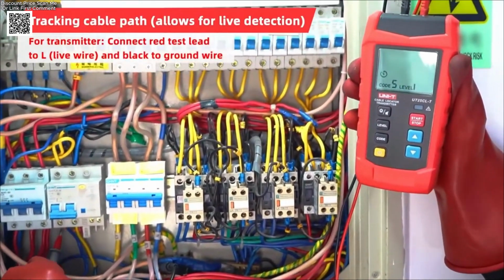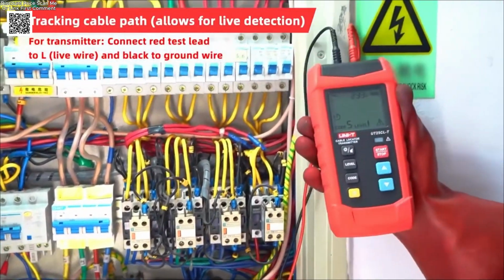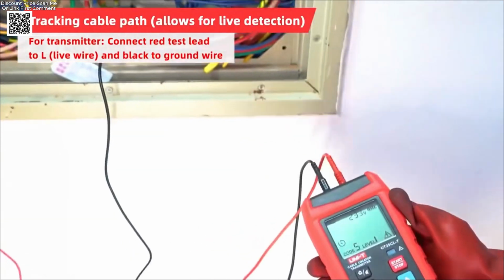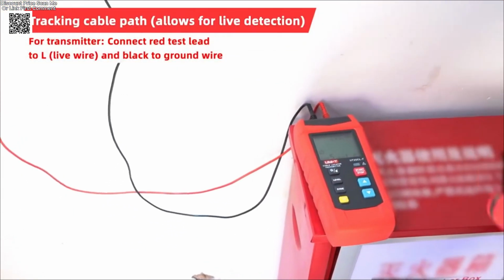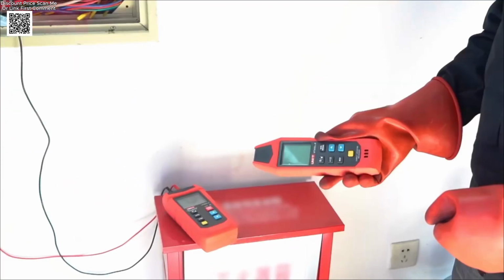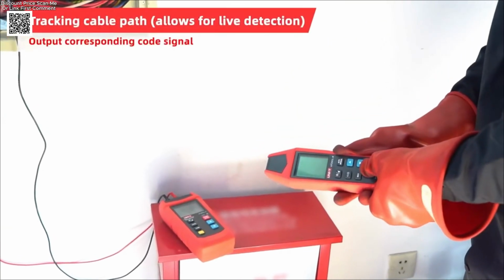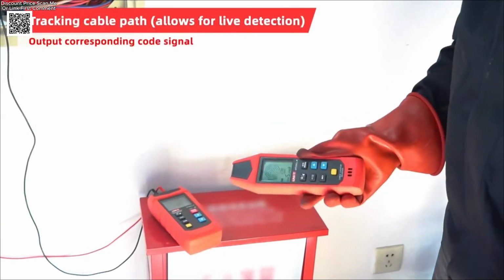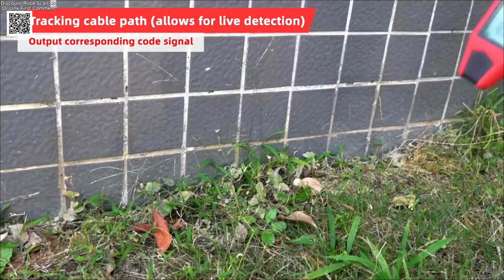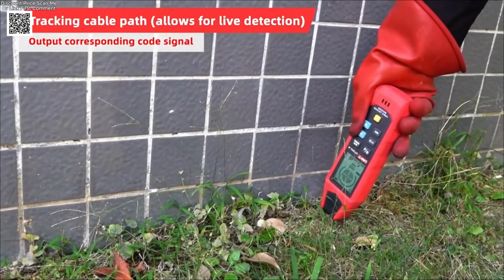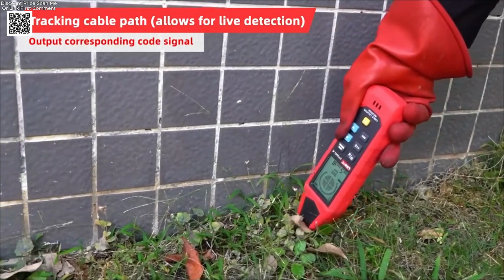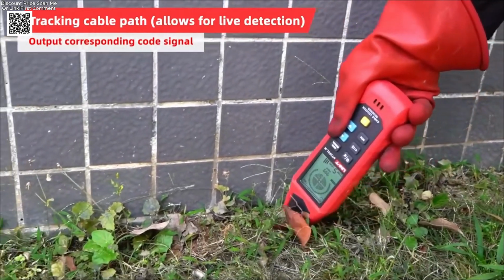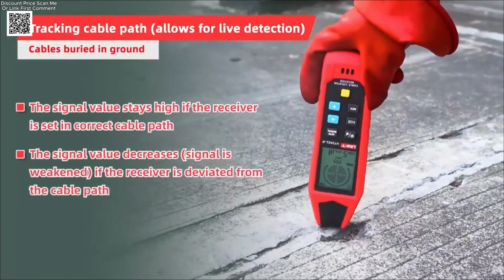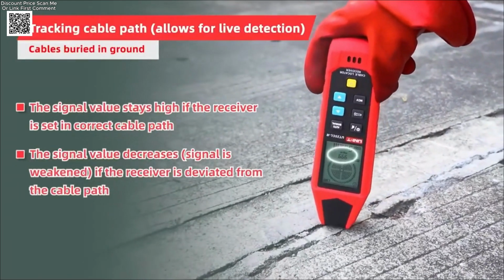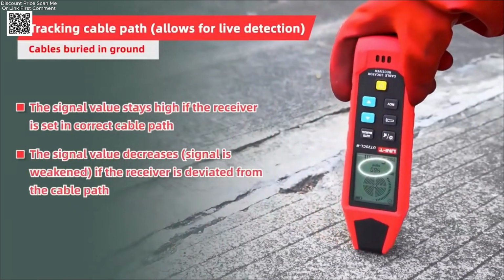Typical jobs for the UNI T UT25CL include mapping the path of a cable behind plasterboard, verifying the route of a buried low-voltage line in the yard, identifying the correct breaker or fuse from a crowded panel, and locating short faults or open breaks on low-voltage circuits. The kit is sized well for field use, with the transmitter around 189 by 96 by 48 millimeters and the receiver around 226 by 68 by 38 millimeters.